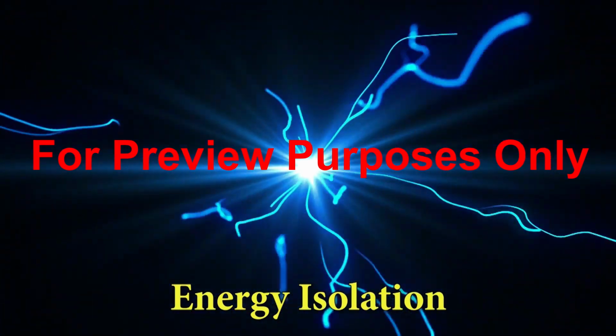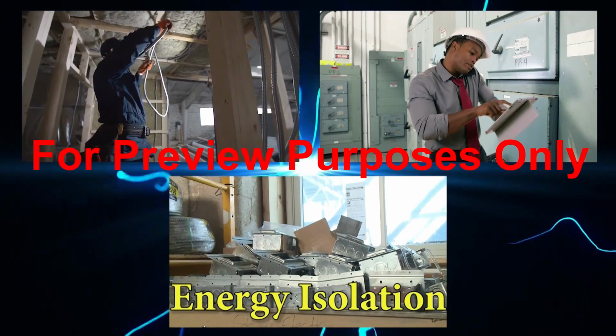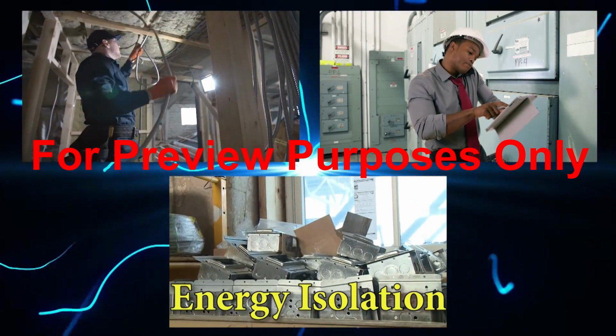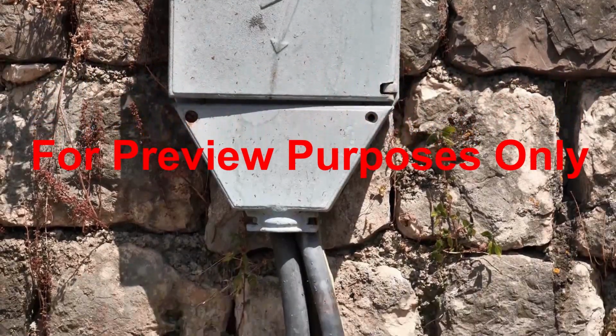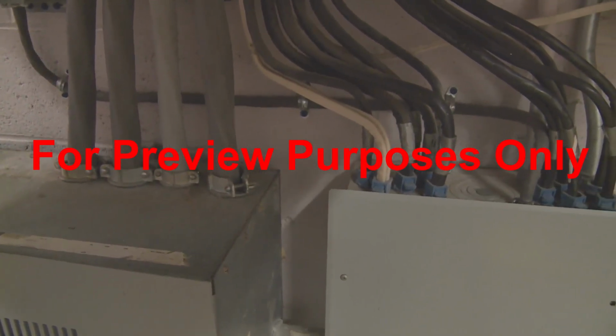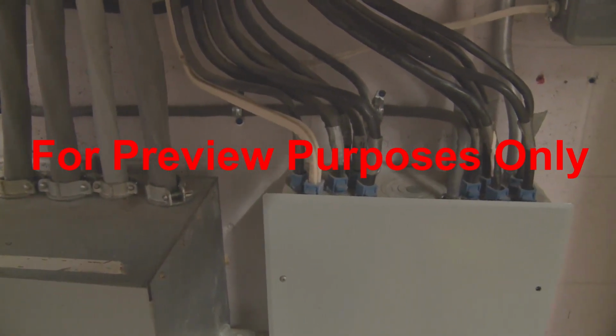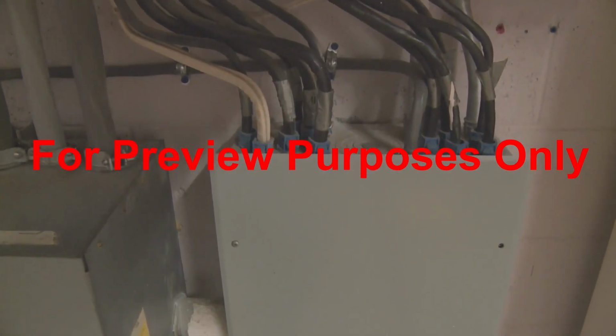Energy isolation ensures that electric current stays safely inside the wires, electric panels, junction boxes, and other equipment that distributes it throughout the site. To prevent damage, wiring should be protected from sharp edges and abrasion wherever it enters panels, boxes, or other fittings. To prevent exposure of energized components, any unused openings in these boxes and fittings should be closed off.